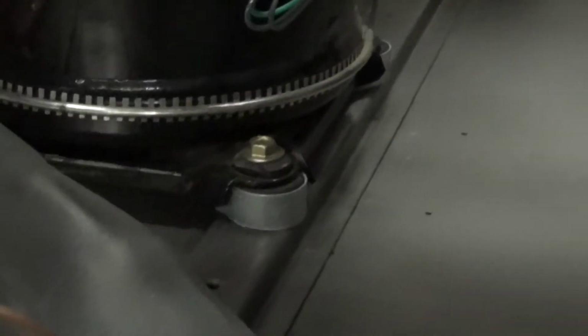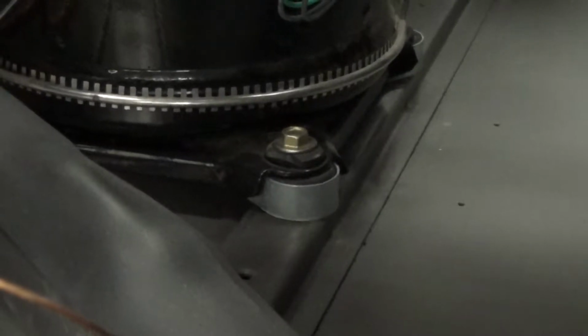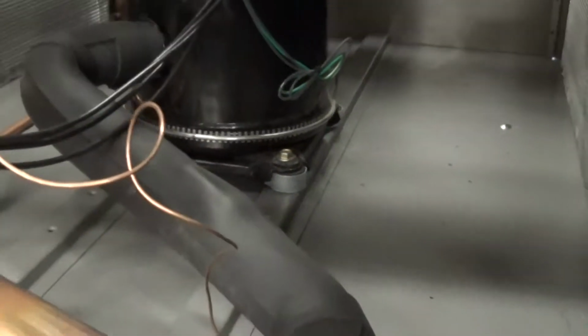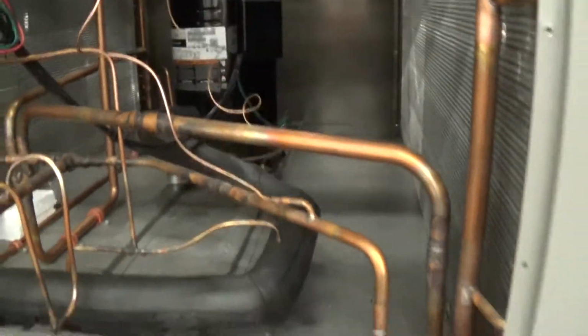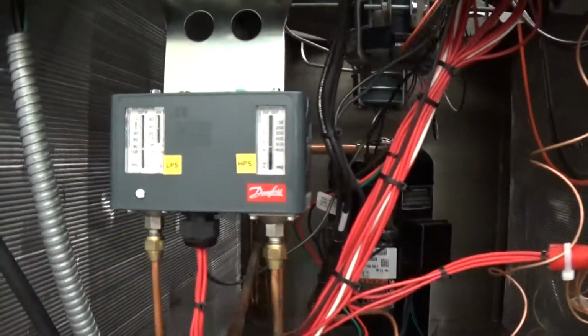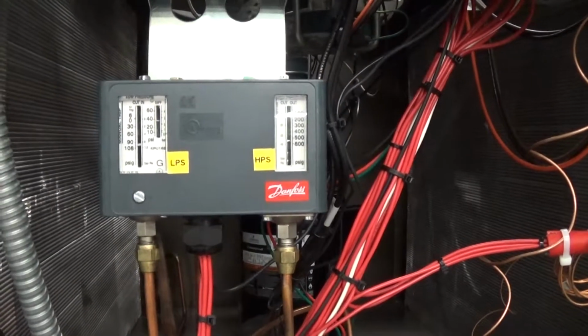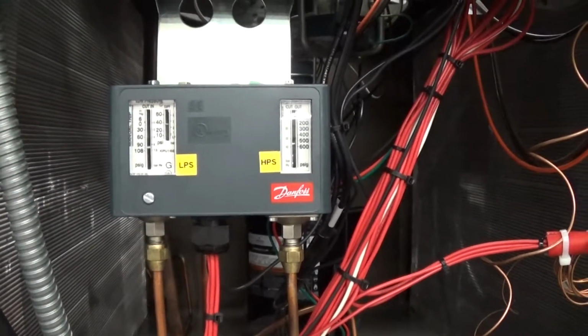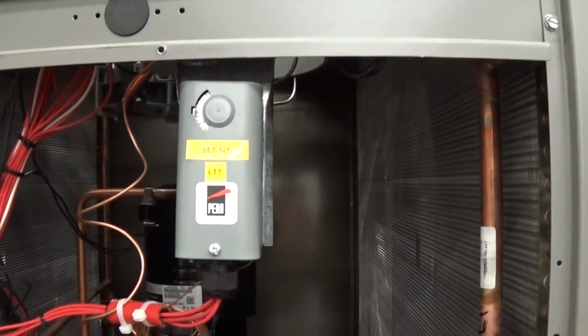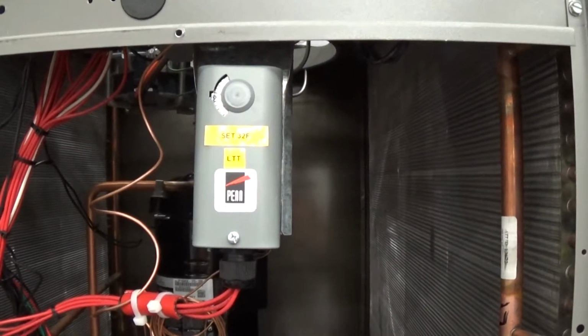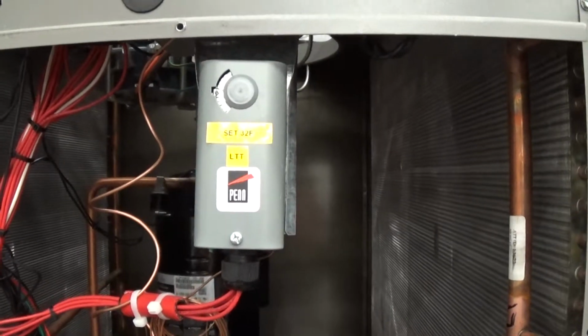Those metal brackets right there, those are shipping brackets. If you loosen up those bolts, those 4 brackets should come out before you run it in its regular intended environment. It's okay to run it a little bit here for the testing that way. It's just going to be a little bit louder as far as the vibration goes. Here we have our high-low refrigerant switches. Those you should not adjust. We also have a freeze stat that senses the temperature of the suction line.